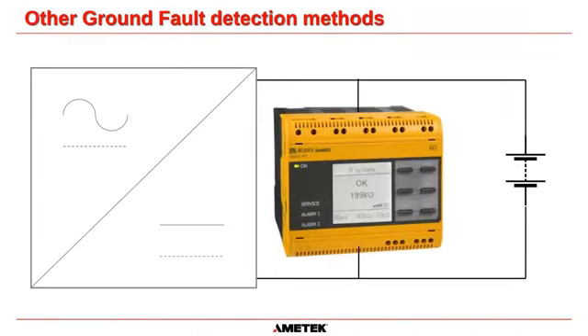I'm not going to go into this design of system, but there is a DC ground fault detector called a Bender, and it does not use a potential divider resistance circuit to monitor grounds. It actually injects, I think, a signal between positive ground and negative ground, and then it detects if that signal comes back the way it should do.